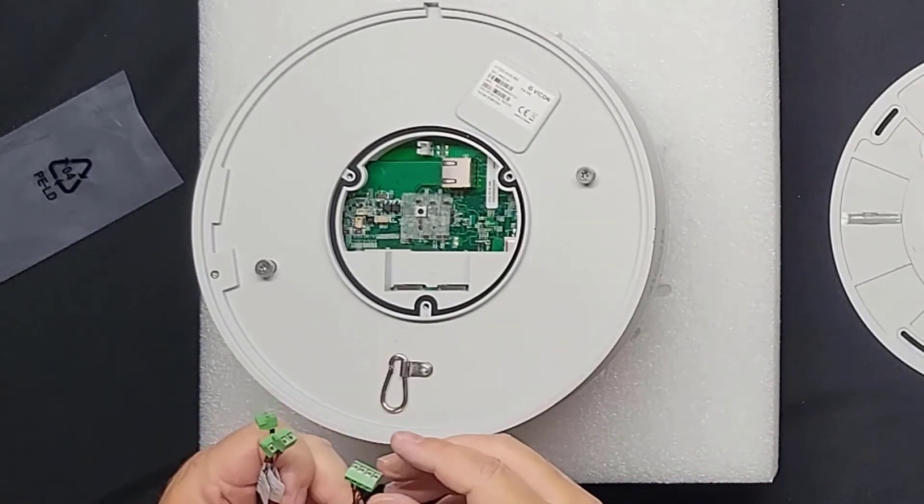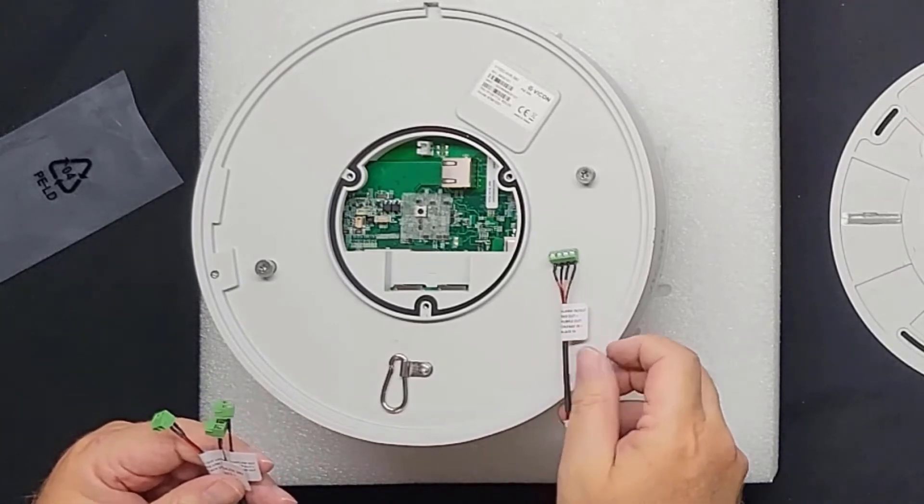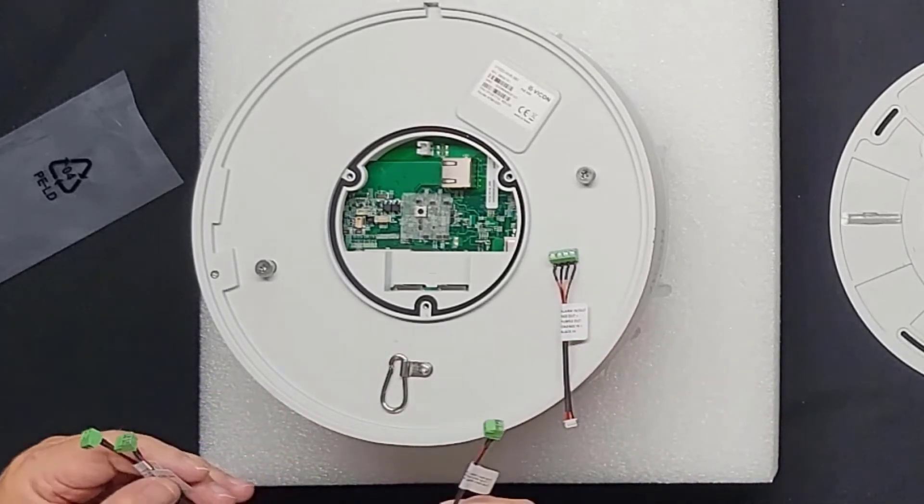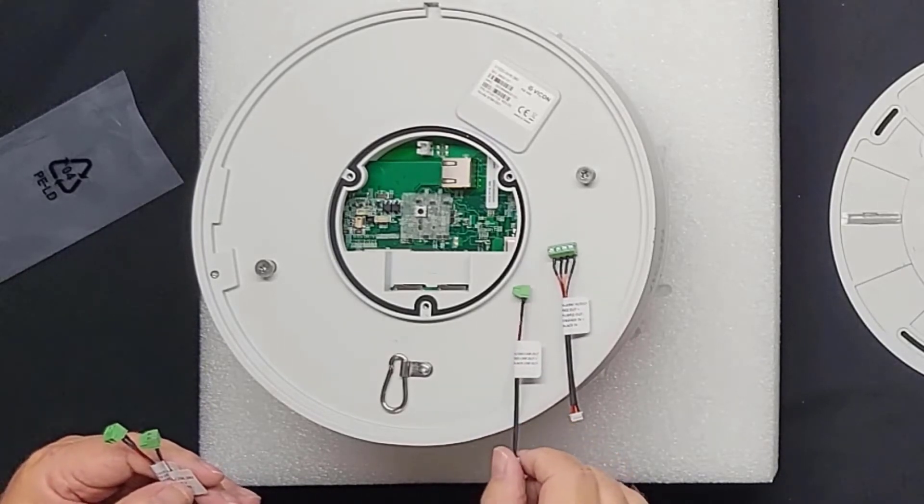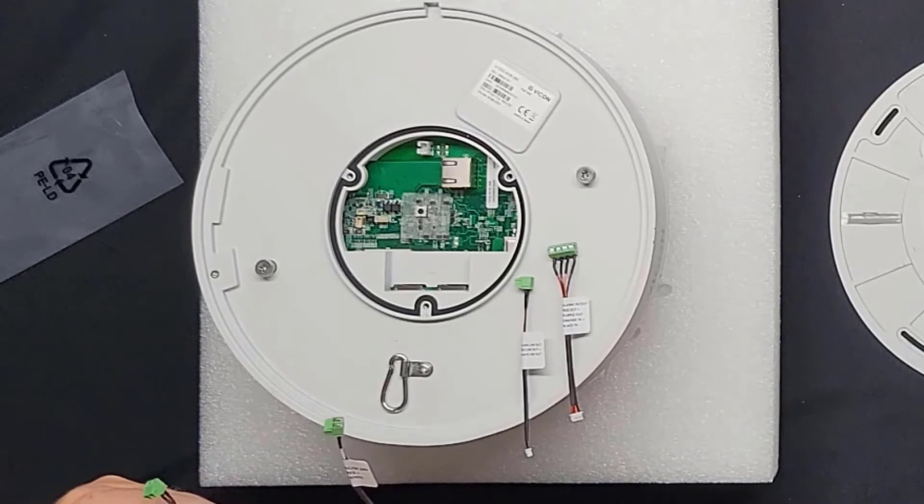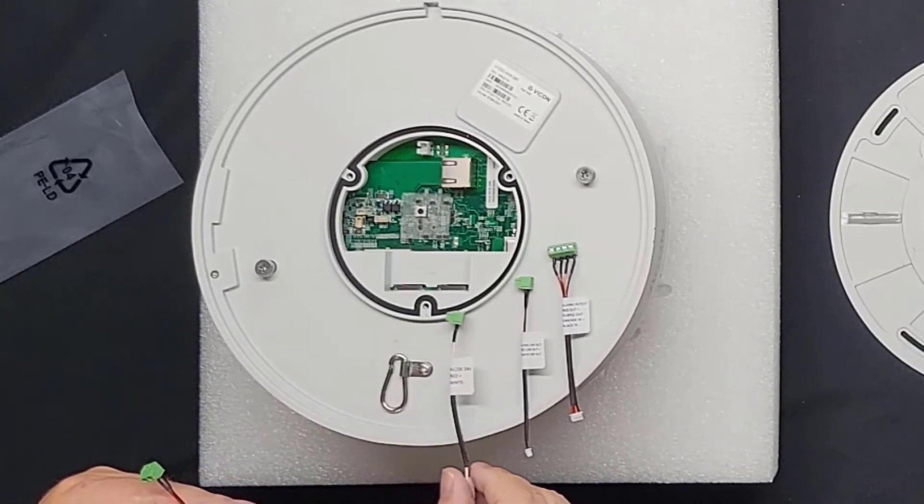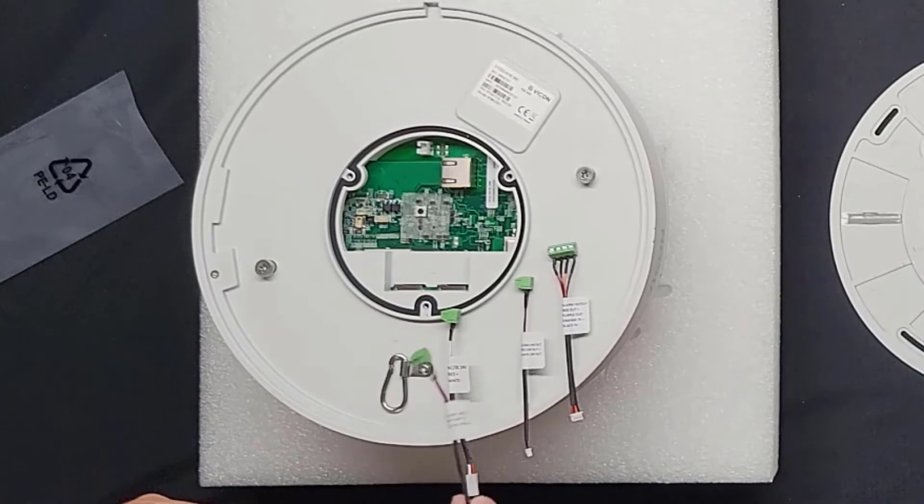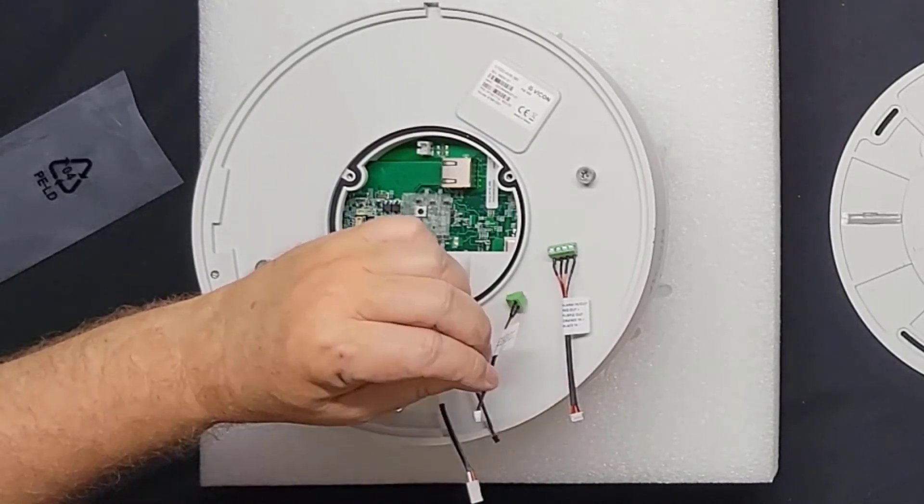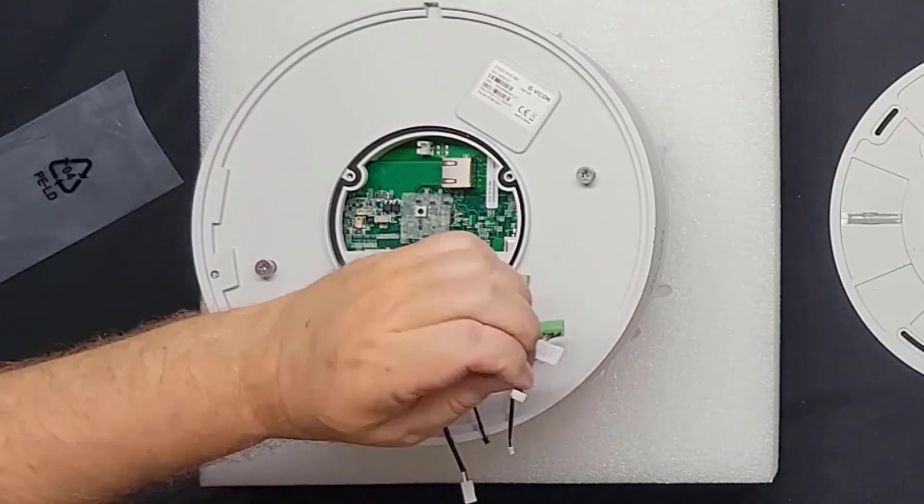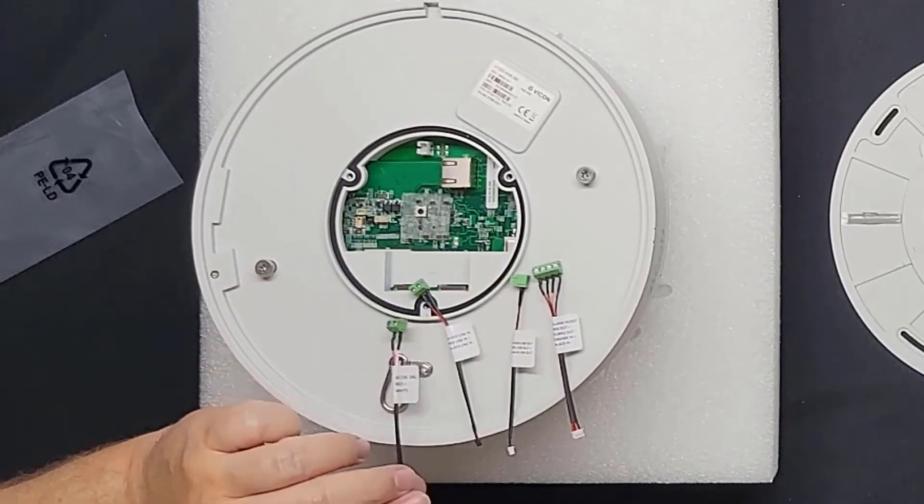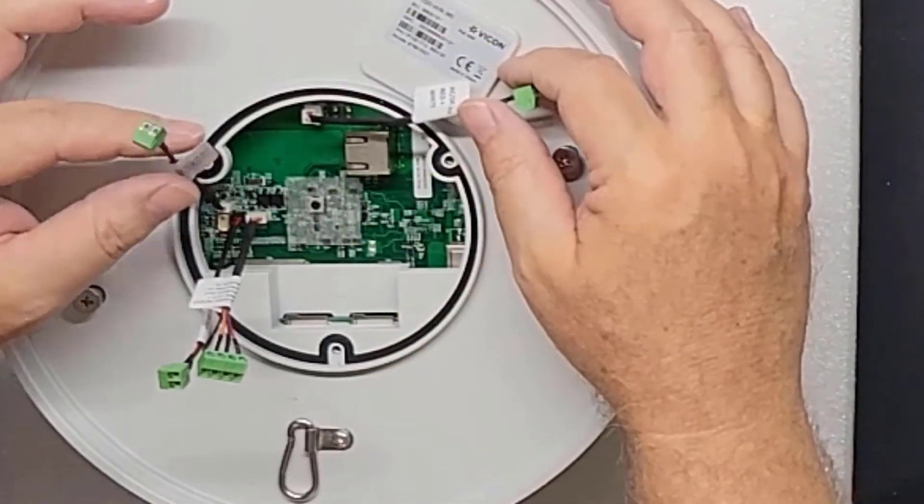Then you would pass an un-terminated multi-conductor wire through that grommet and make connection to the connectors I'm about to show you. We'll take the access cover off and look inside, and we see all of our connectors for alarm in, alarm out, audio in, audio out, and we provide for you the pre-made cables to use for these functions. These cables and connectors should not be passed through the grommet.